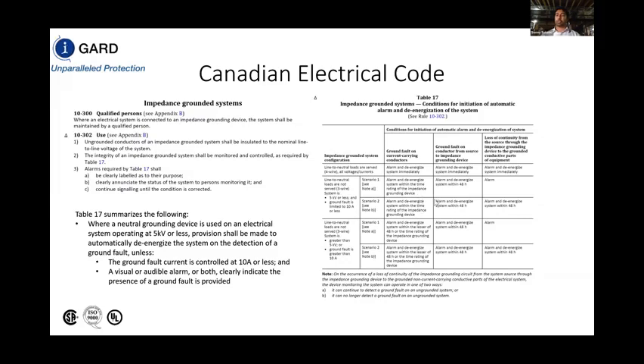For the short circuit scenario, we have to alarm and de-energize the system within 48 hours. And with the open circuit scenario, we either alarm if we can still detect a ground fault in an ungrounded system, or we have to alarm and de-energize the system within 48 hours.